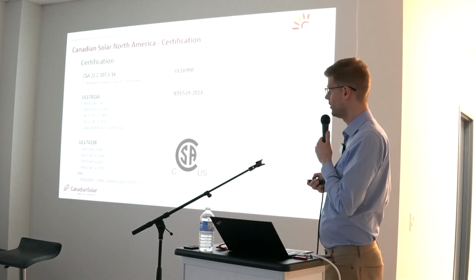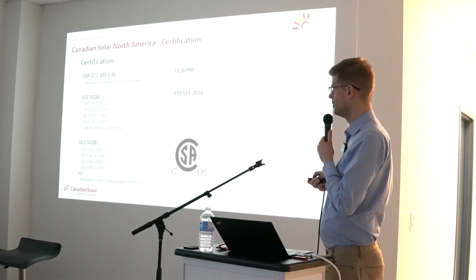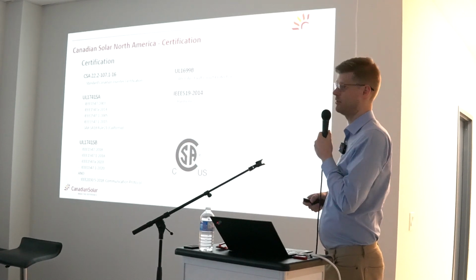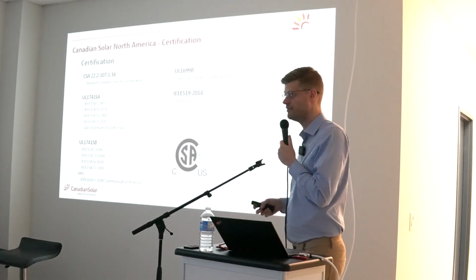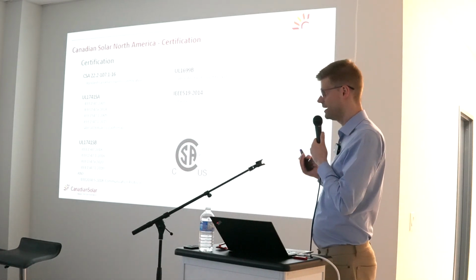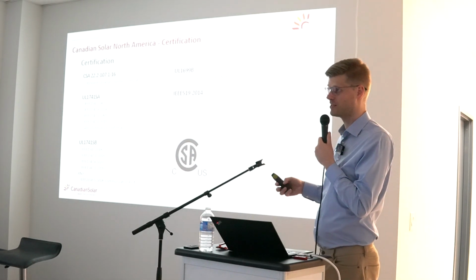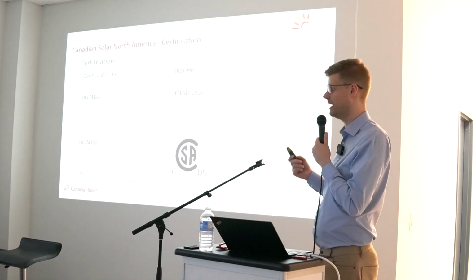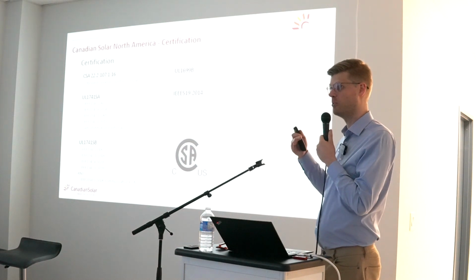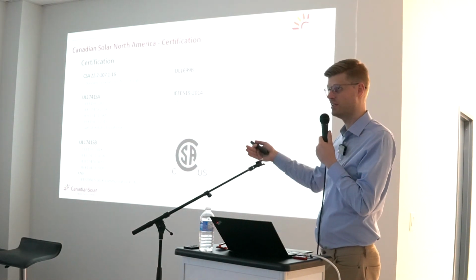Besides SB, it also has a bunch of other certifications, all the way to the newest grid code, the 2021 IEEE 1547, and the communication protocol for integrated SCADA that is predefined. None of the utility companies at the moment are using that SCADA protocol, but the inverter has it; it is already tested and certified with it. So for future projects, whenever the utilities are ready to implement a gateway that speaks that communication protocol, you can simplify the communication between your system and the utility for bidirectional communication.